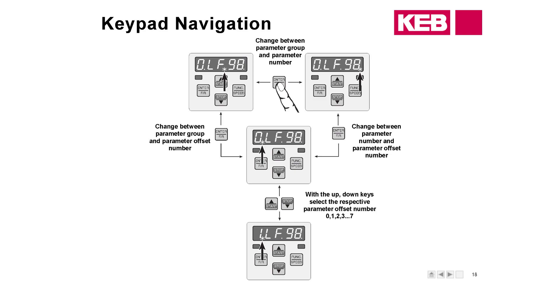If you wish to reset the fault log — for example, when troubleshooting and you want to know whether faults happened an hour or a day ago — go to 0 LF 98, hit Function to view the fault, hit the up arrow to scroll to 10, and hit Enter. That will load 'No P' into all of the fault log parameters so you can tell whether you're getting a new fault going forward.